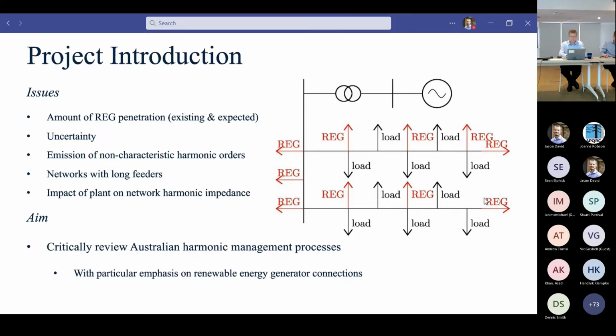Other issues include non-characteristic harmonic orders. The development and management of harmonic distortion ultimately prioritizes a subset of harmonic orders, but present day and emerging technologies are actually comparatively high emitters of non-characteristic harmonic orders, so consideration of these emissions needs to be thought about. Also, networks here in Australia with long feeders and transmission systems have resonances, impacting overall network harmonic impedance and how we best manage distortion in such scenarios.